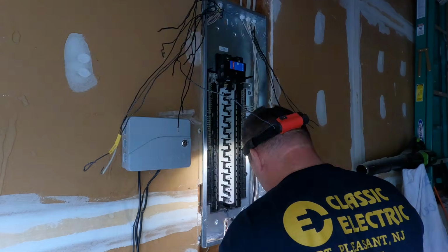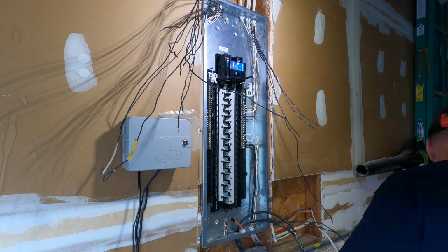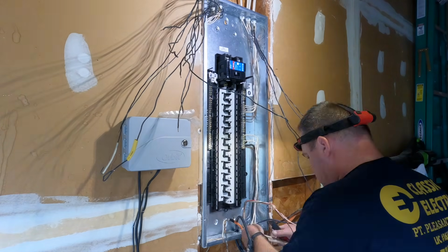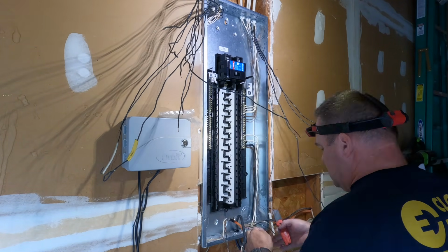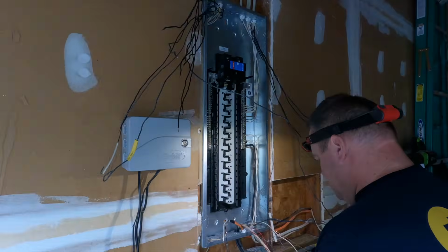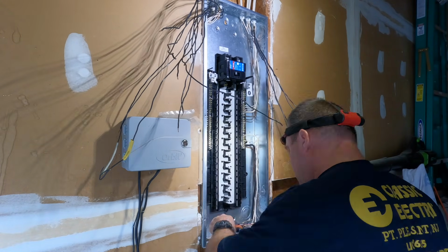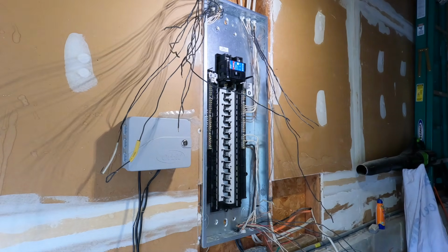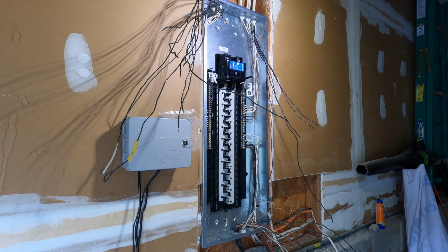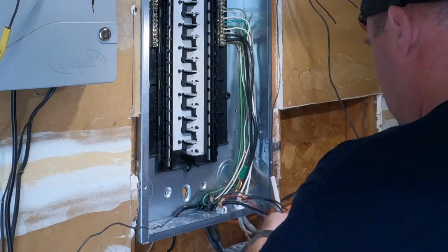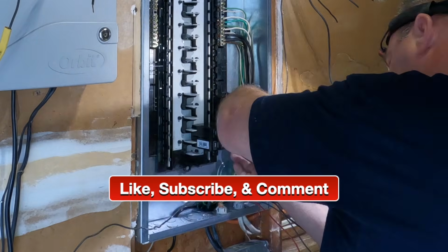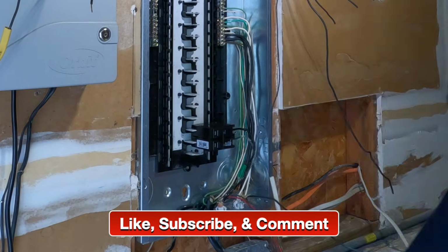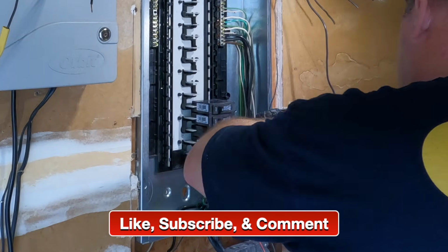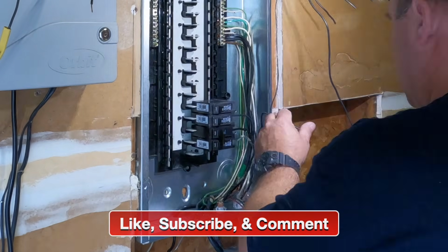So a few code cycles ago, maybe 10, 15, I don't think it's been 20 years, but in some of the old panels you see a lot of doubled up neutrals. We cannot do that today, so that was a good safety change for sure. I like to keep all my circuits coming into the bottom of the panel, and that's what all these circuit breakers at the bottom here are for.